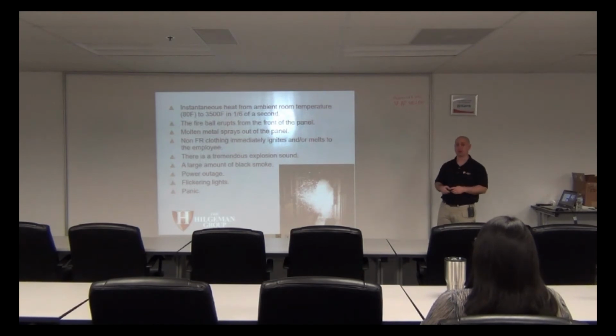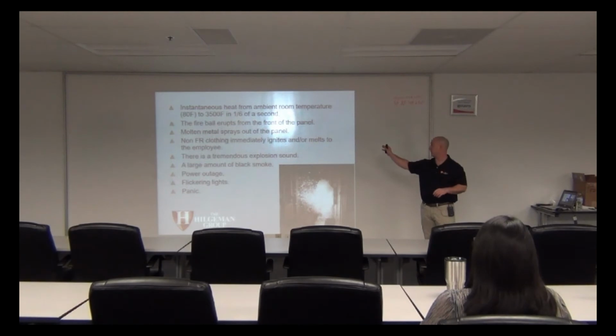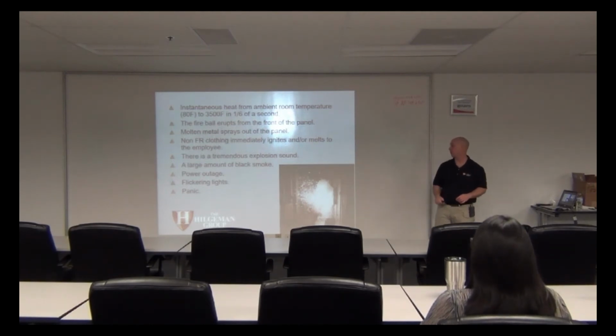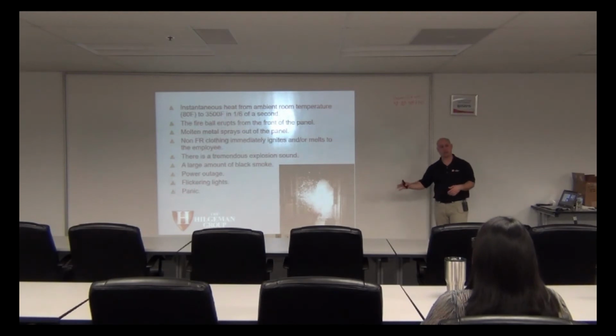Instantaneous heat from ambient room temperature—basically 0 to 3,500 degrees. It says ambient room is about 80, though I don't know if I agree with that all the time; it depends on the state of the room and what you keep it at. But it goes to 3,500 degrees in a sixth of a second, so it's going to be a fireball that comes out. We'll see a video of a really significant arc flash—it's like an explosion. Big fireball. All the metal within that enclosure that melts will be forced out of the panel onto anything on the outside.